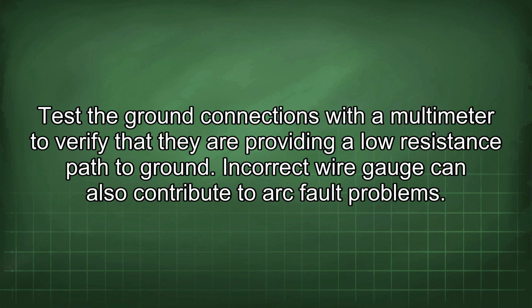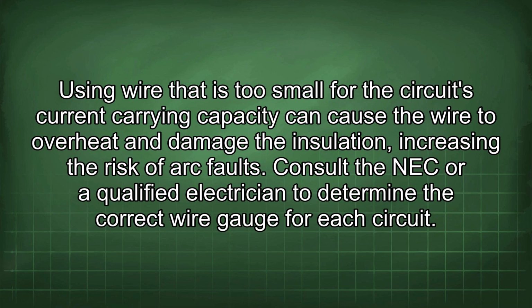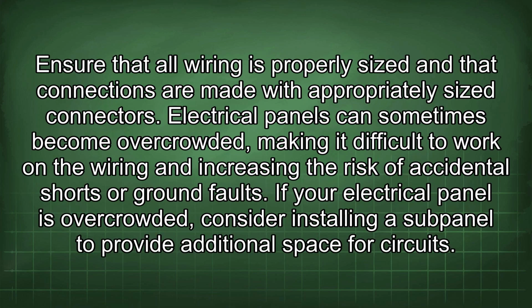Incorrect wire gauge can also contribute to arc fault problems. Using wire that is too small for the circuit's current carrying capacity can cause the wire to overheat and damage the insulation, increasing the risk of arc faults. Consult the NEC or a qualified electrician to determine the correct wire gauge for each circuit. Ensure that all wiring is properly sized and that connections are made with appropriately sized connectors.